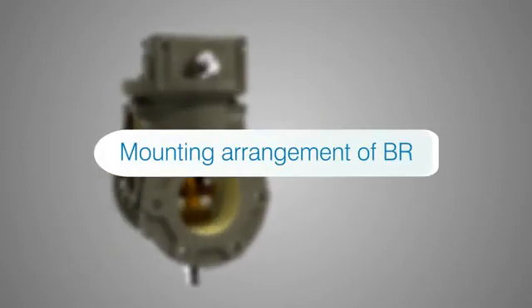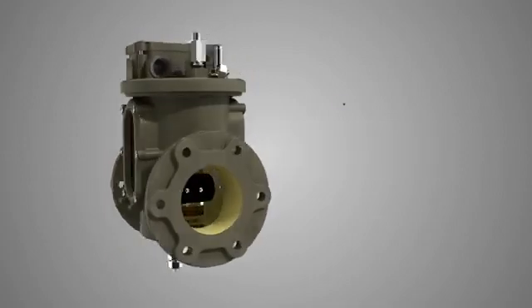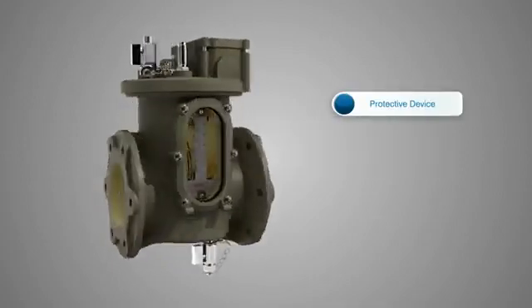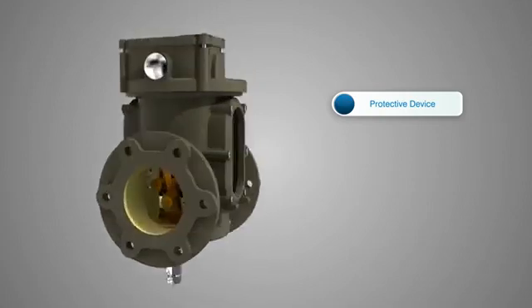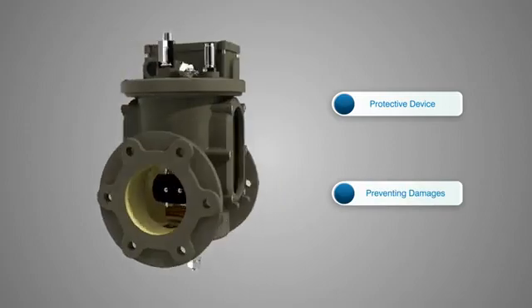Mounting Arrangement of BR. The Buchholz relay is used as a protective device for detecting fault conditions developed inside the transformer and preventing damages by operating an alarm or a trip system.